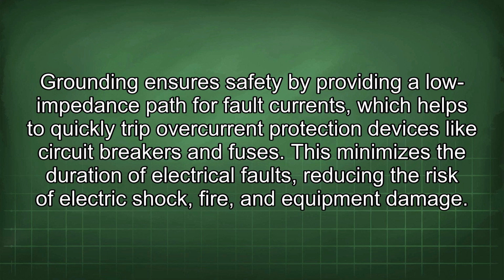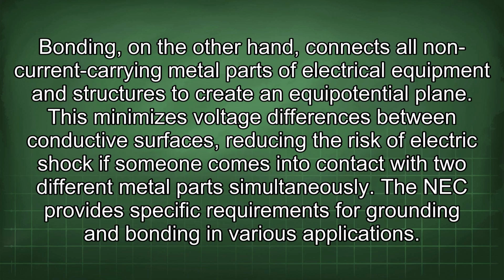Grounding ensures safety by providing a low impedance path for fault currents, which helps to quickly trip overcurrent protection devices like circuit breakers and fuses. This minimizes the duration of electrical faults, reducing the risk of electric shock, fire, and equipment damage. Bonding, on the other hand, connects all non-current carrying metal parts of electrical equipment and structures to create an equipotential plane. This minimizes voltage differences between conductive surfaces, reducing the risk of electric shock if someone comes into contact with two different metal parts simultaneously.